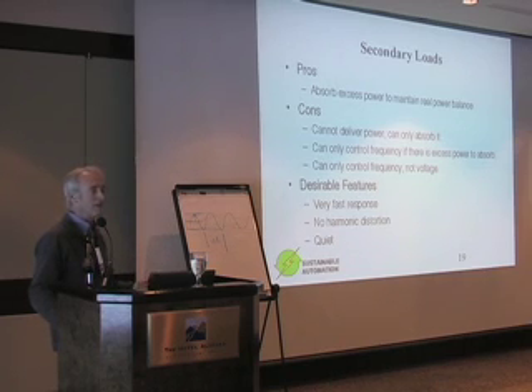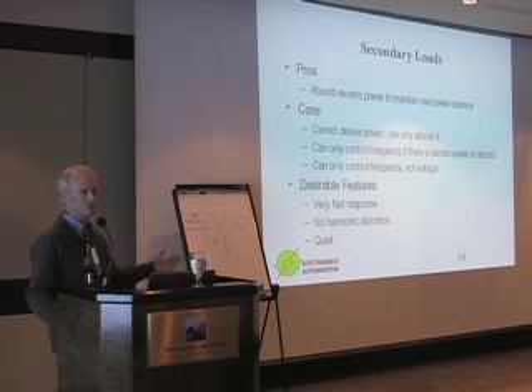Another thing is that there have been different implementations over the years of secondary loads. Some led to very poor power quality. People have gone away from phase control, power control, because that introduces a lot of harmonics and poor power quality on the grid. So one thing you want to look for in a secondary load controller is something that does not distort the waveform and doesn't introduce any harmonics that might propagate to either your diesels or to customer loads.